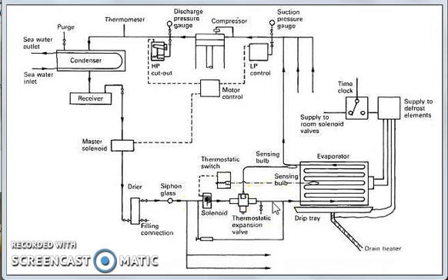This is in case we really want to isolate a particular room. Normally we check which room is creating a problem, like where the gas leakage is. We can close this room and this room manually, and we can check whether the leakage is over here or in the room, and whatever the places it may be. So one manual valve is over here and one manual valve is over here.